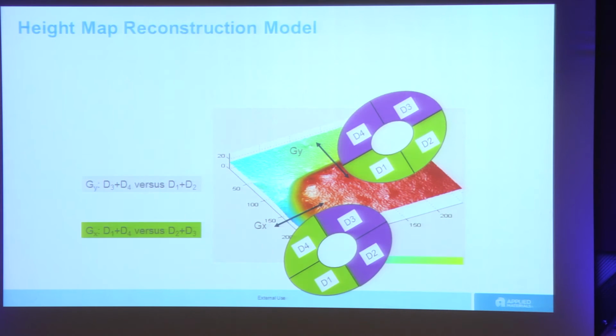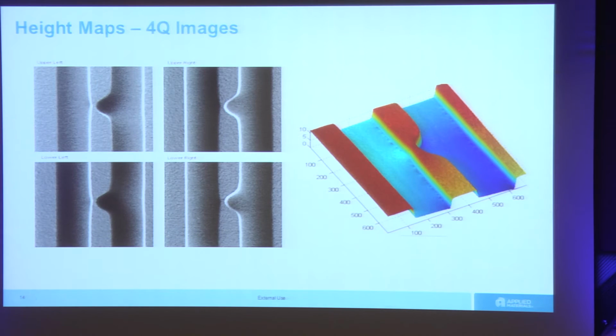And this is more or less how it works. So if you go pixel by pixel and calculate the gradient from the amount of electrons that are distributed between the detectors, and then sum the gradients, so it's a height from gradient method, and you get your three-dimensional shape. So this is how our 4 quadrants images look like, and this is the 3D model reconstructed from them.